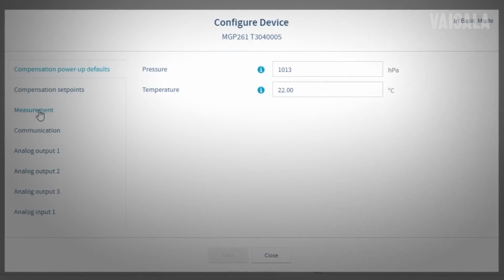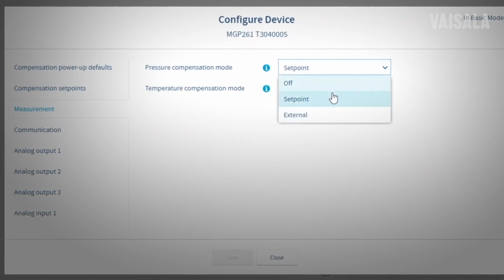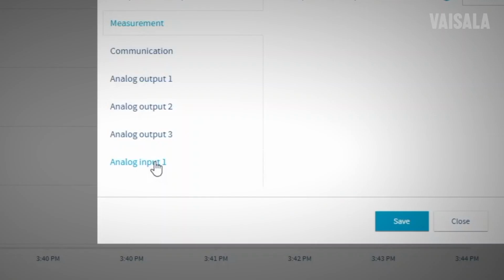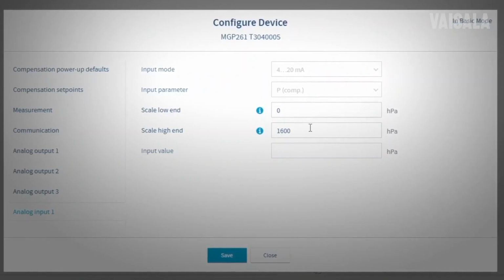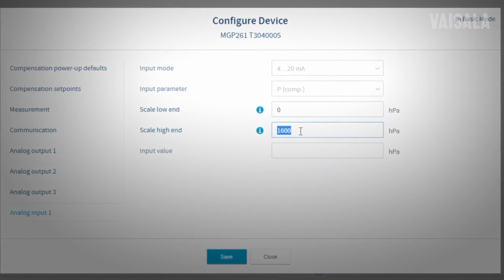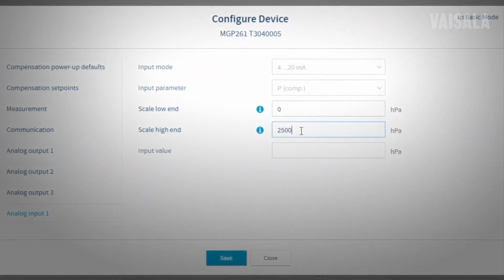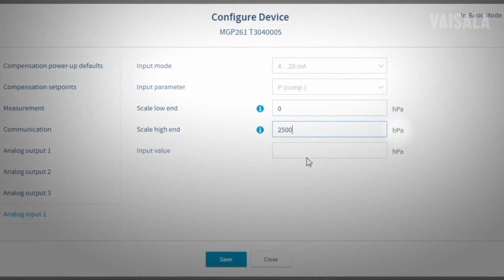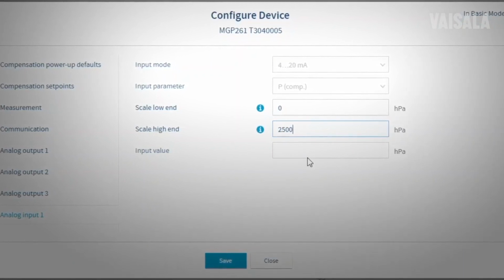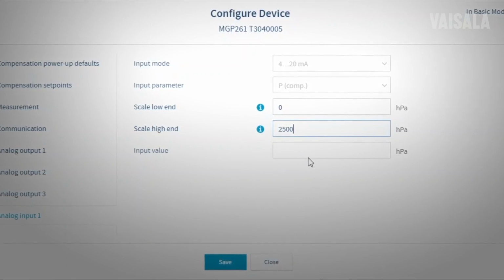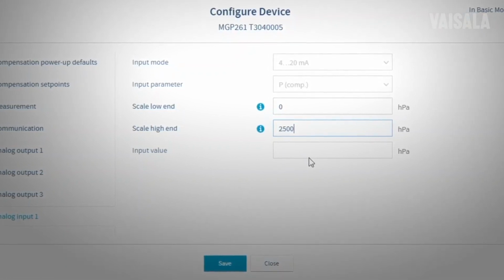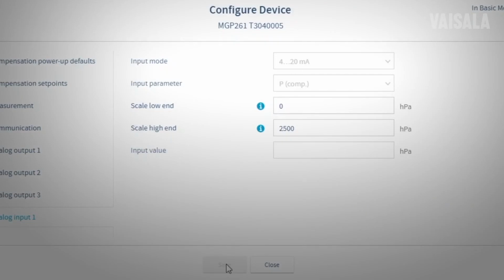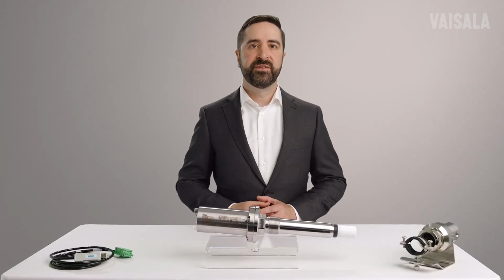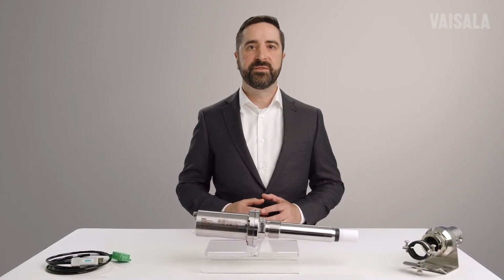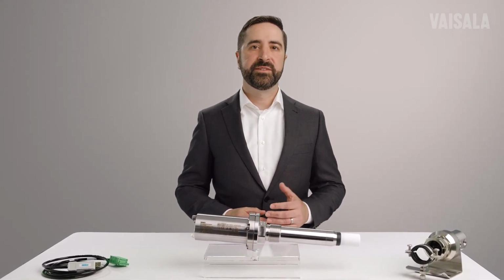When using an external sensor, you'll choose External for the compensation mode in that Measurements tab. From there, you'll head to the Analog Input tab at the bottom of the menu and confirm that the measurement scale of the external sensor you're using is reflected accurately. Again, this value is reported to the software in hectopascals, which is an absolute pressure value and equivalent to absolute millibars of pressure. Once complete, save and exit the menu unless you're making any other changes to the probe settings. Changing these settings does not affect the unit's calibration and requires no further service or calibration before final or reinstallation.